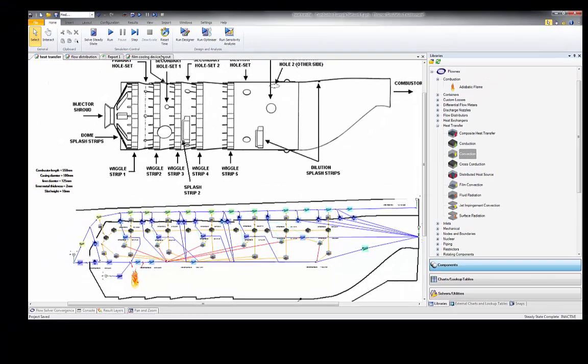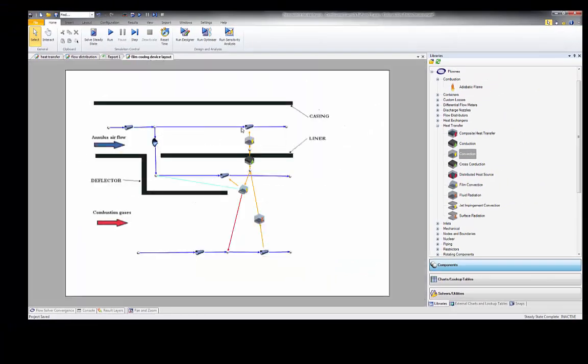Let's take a film cooling device layout as an example and look a little closer. From the combustion gases we have a radiation component accounting for fluid radiation, a film cooling component cooling down the same surface to which the hot gas is radiating, a conduction element accounting for conduction through the liner wall, and convection to the annulus air flow cooling the cold side of the liner. You can model in as much or as little detail as you want, depending on the modeling assumptions you've made.